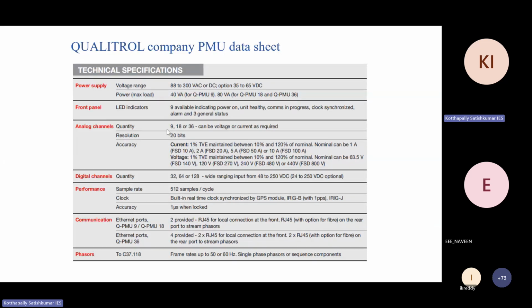And analog channels, as I told, analog channels means what? Your CTPT inputs. Digital channels will tell whether the CB is open or not, whether the relay is functioning or not. These are the digital channels. 1 and 0 are the digital inputs, whereas analog channels are your voltage and currents, the analog inputs. Here the accuracy is in the range of 1% TVE. TVE means total vector error, which for current is 1% accuracy. For voltage also, the total vector error is in the range of 1%.